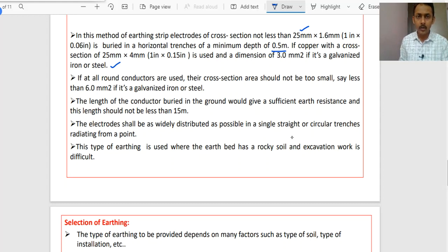If it is copper, the cross-sectional dimensions are 1 inch by 0.15 inch. If it is galvanized iron or steel, some 3 mm square will be used. So depending upon the material you are using, these are to be preferred. Now if round conductors are used, their cross-sectional area should not be too small, say not less than 6 mm square if it is galvanized iron or steel. The cross-sectional area should not be very small; it should be as large as possible. And the length of the conductor buried in the ground should give a sufficient earth resistance, and this length should not be less than 15 meters.